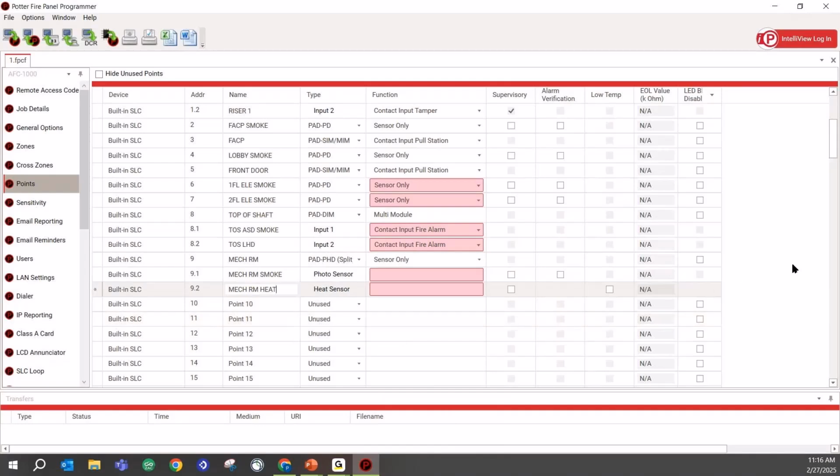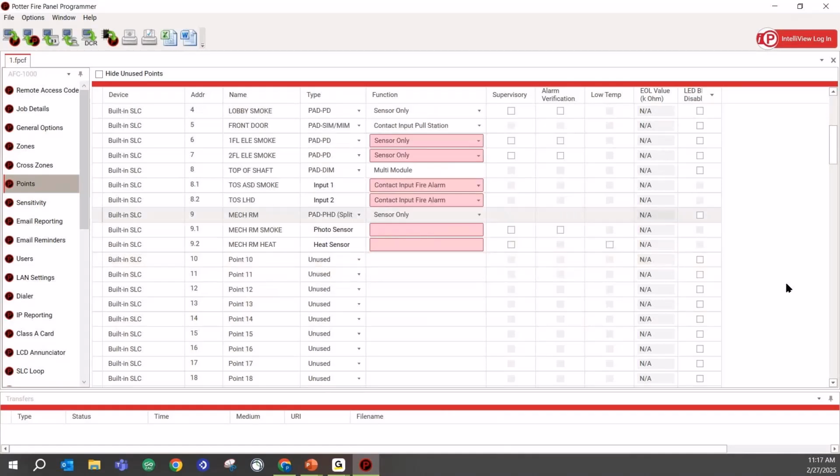So mechanical room, we're generally not going to have those sort of environmental concerns. So we'll go ahead and use that there. And we'll say that 135-degree heat is acceptable for that application. If we need a higher level of heat detector for that mechanical room because of the sprinkler heads that are going to be getting put in, then we would want to go with just a pad HD. All right, so that takes care of the initiation side of elevator recall.